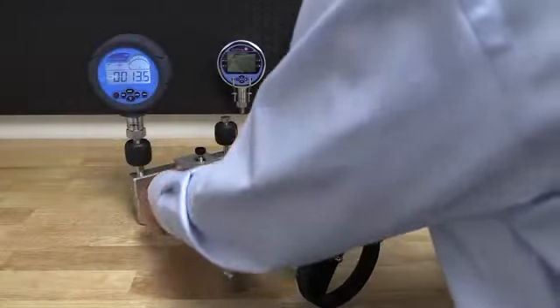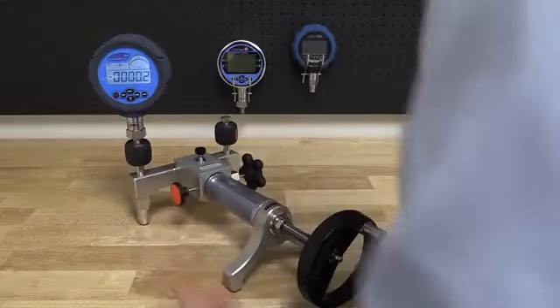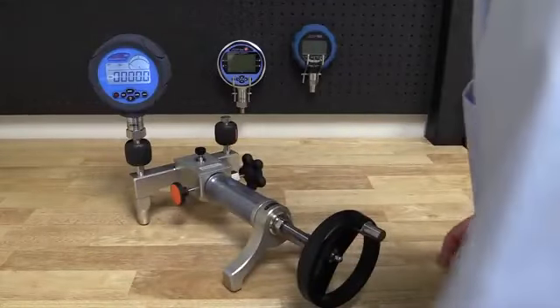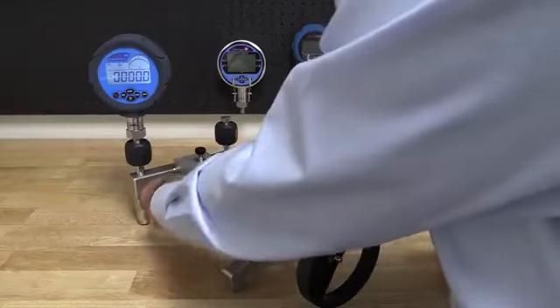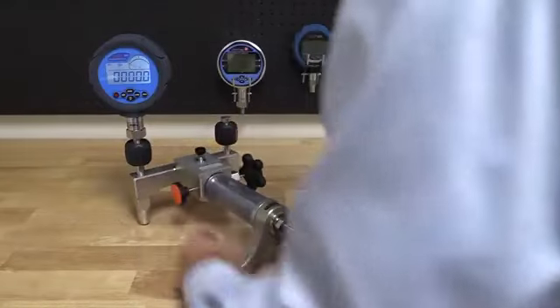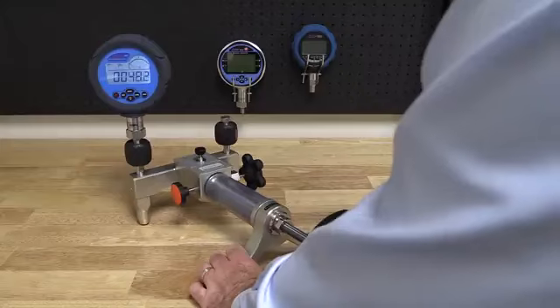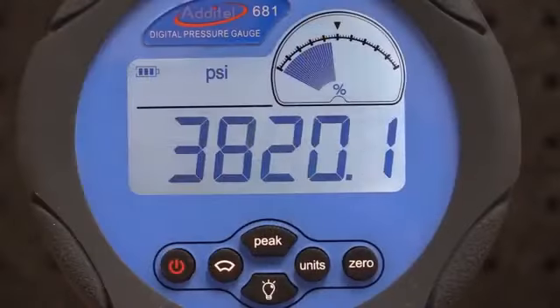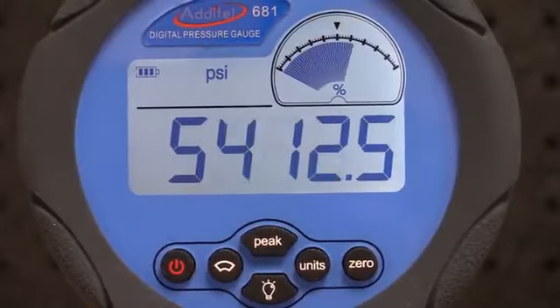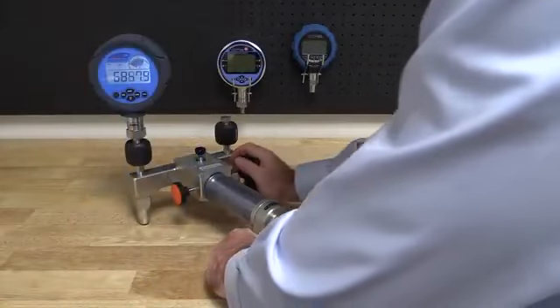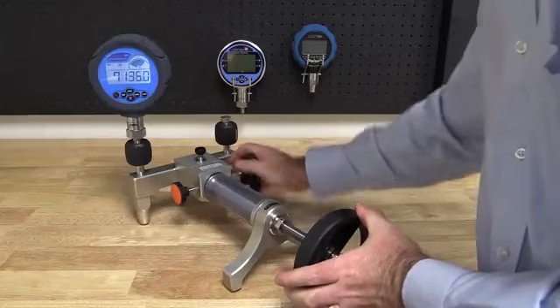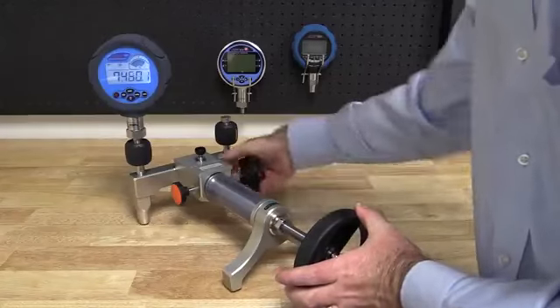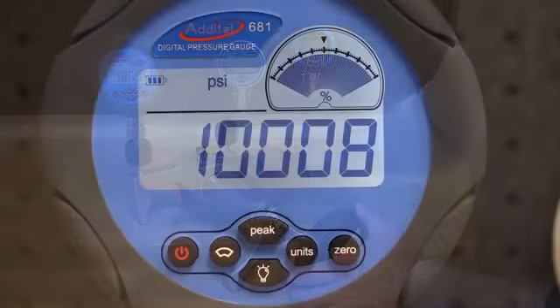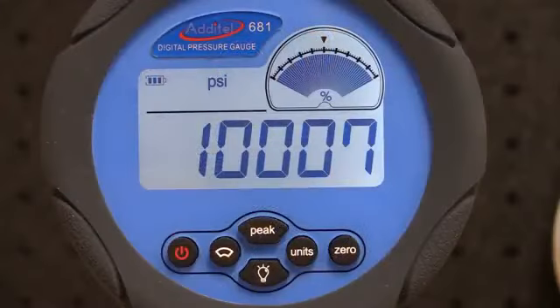Once you see a good vacuum being pulled and very few bubbles emerging in the liquid reservoir, then we are ready to start generating pressure. You should easily be able to generate full-scale pressures with less than half the stroke of the main screw press. For higher pressures, we need to use the high pressure or fine adjustment knob to generate the remaining pressures and dial into a cardinal point. At the high pressures, it may take a few minutes for the measurement to stabilize. Small adjustments using the fine adjustment knob may be needed to ensure that you achieve the cardinal point.